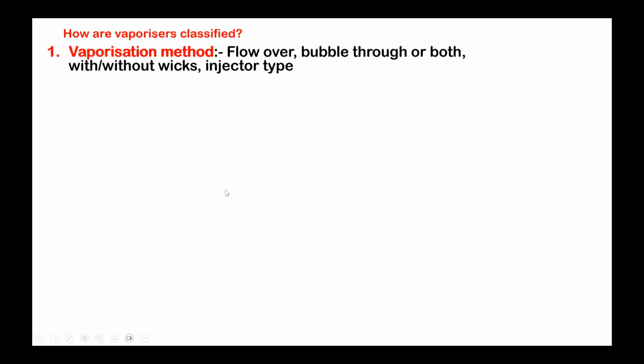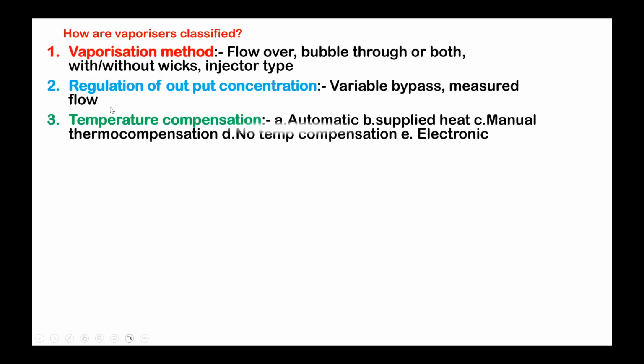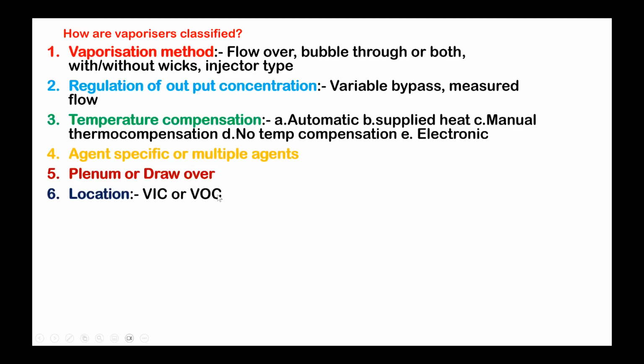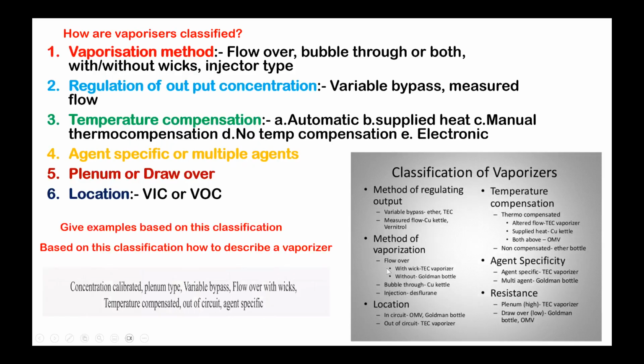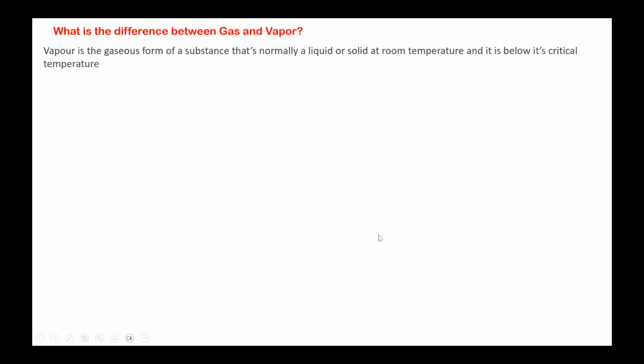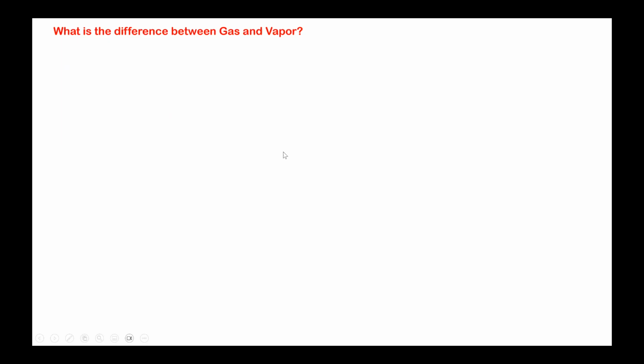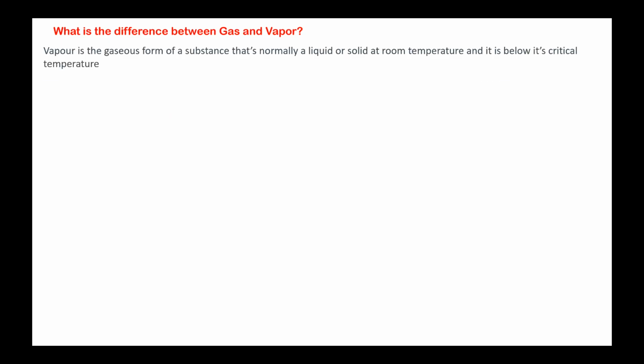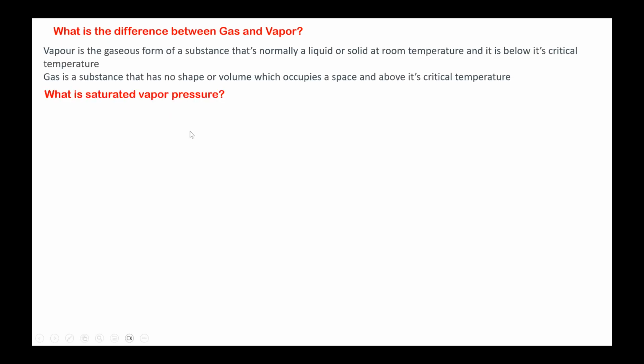So, vaporizer classification: how they are classified based on vaporization method, regulation of output, temperature compensation, agent specific or multiple agent, and plenum or draw-over location. This is the classification, and we have examples for all of these. What is the difference between a gas and a vapor? Above the critical temperature it is a gas, and below the critical temperature it is a vapor. A gas is a substance that has no shape or volume and occupies the space above its critical temperature.